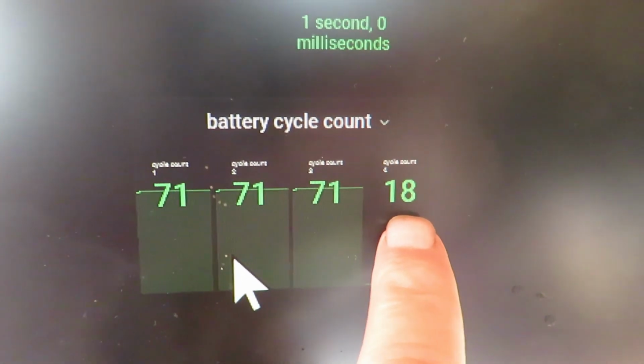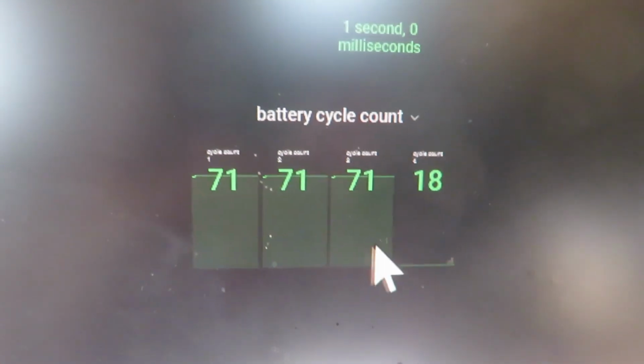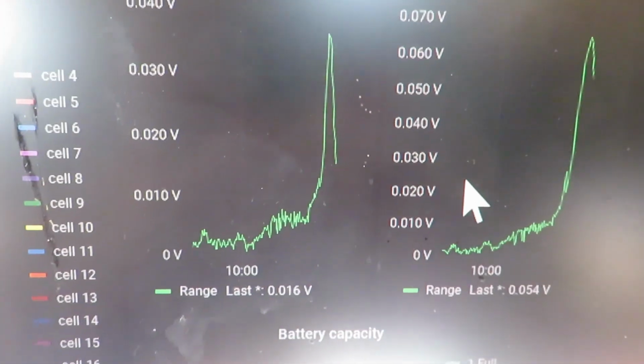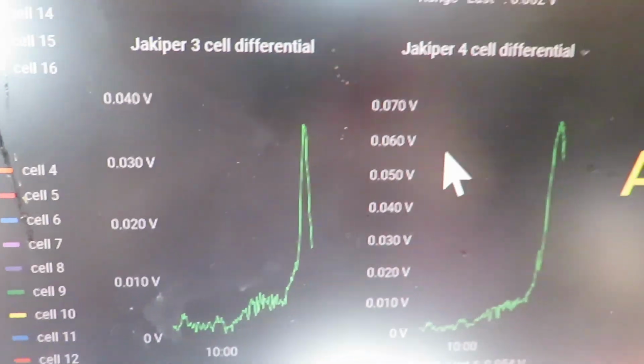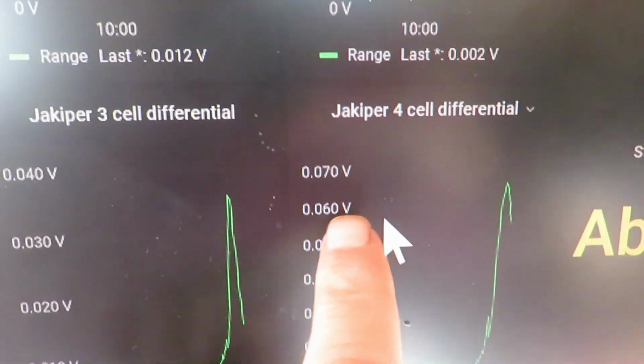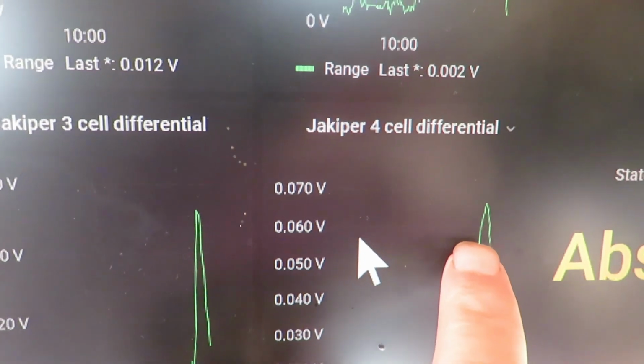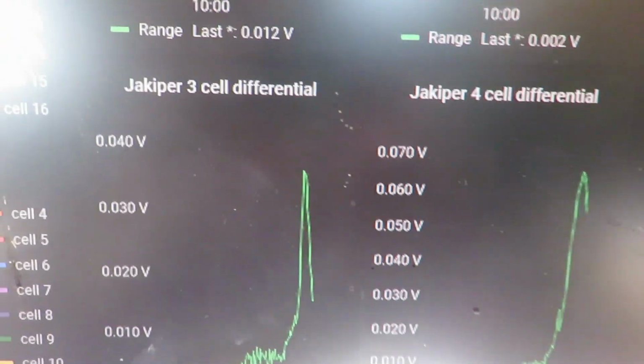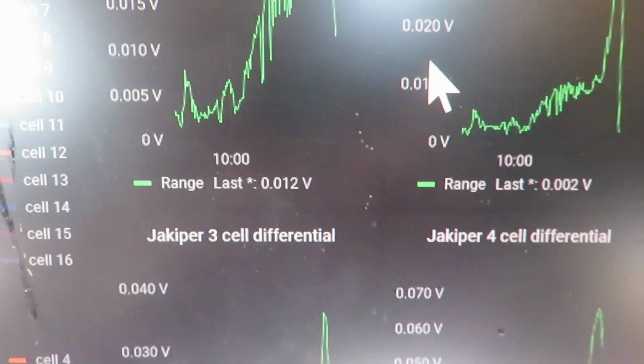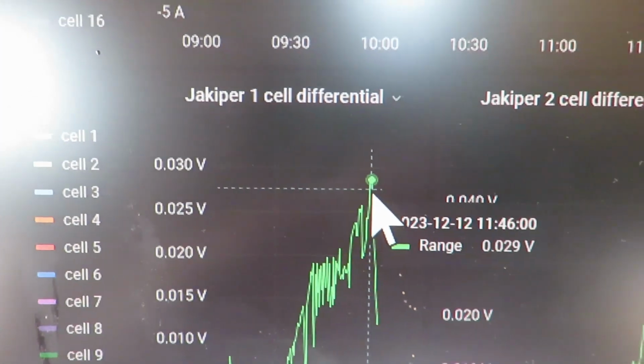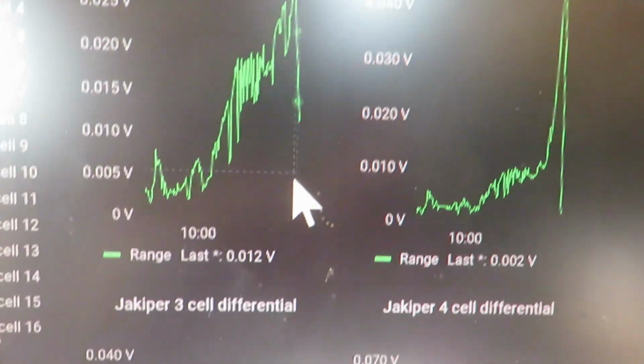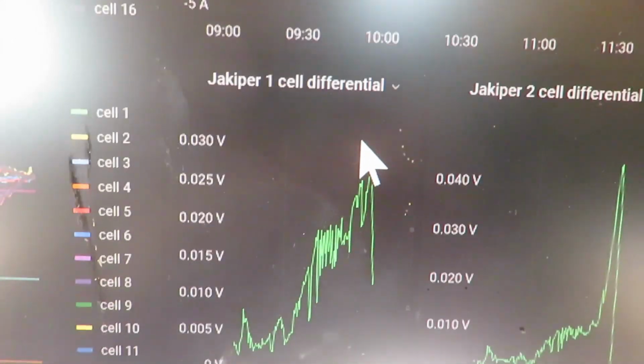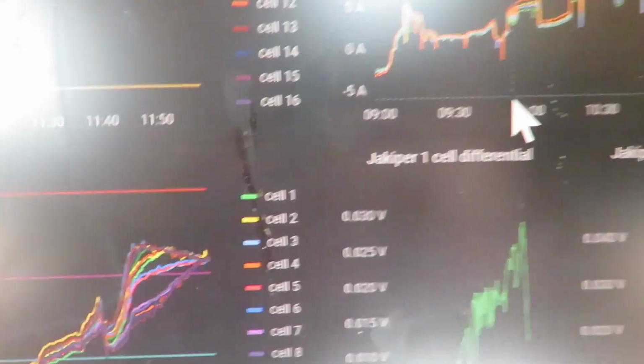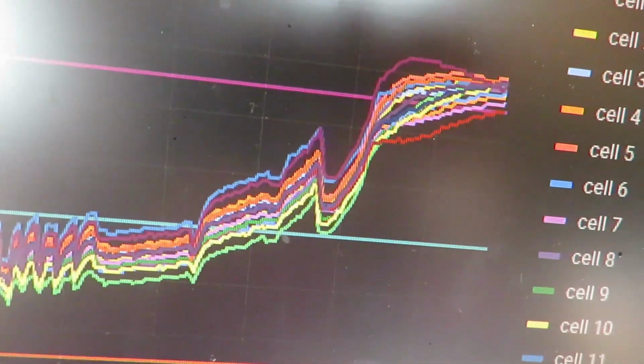You can see these batteries are all the same. This one I got a year later, so that's why it has less cycles on it. And the differentials aren't too bad - battery 4 is only up at like 65, and the others only got up to about 30 or 40 differential. Ideally they'd be 1 or 2, but that takes some messing around to balance them all.